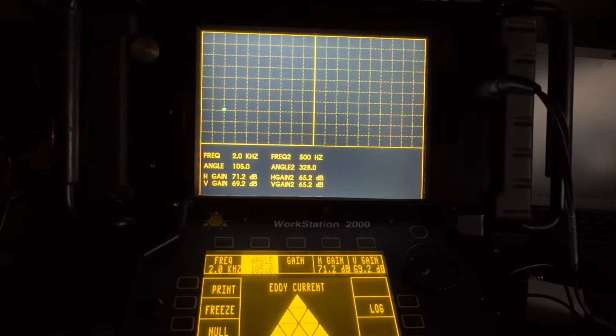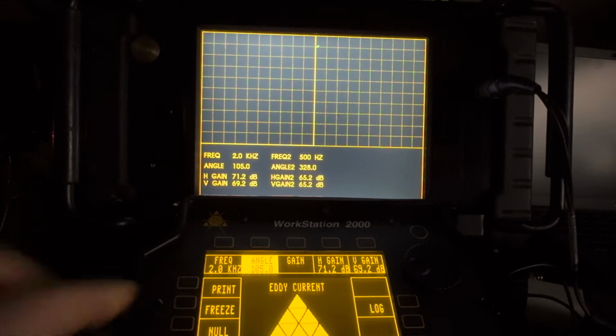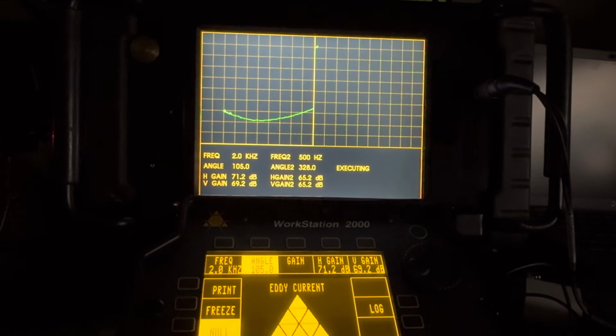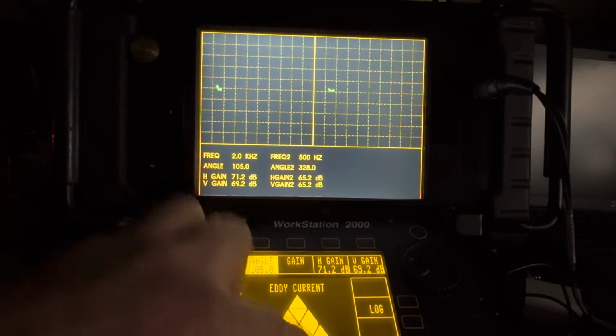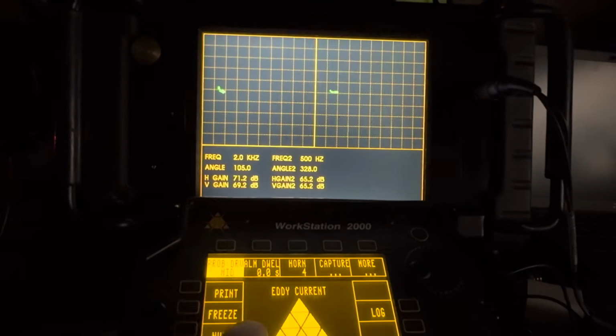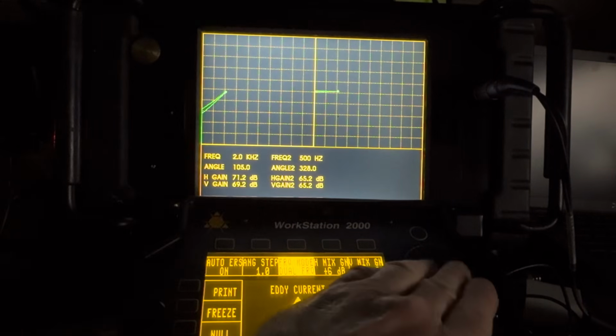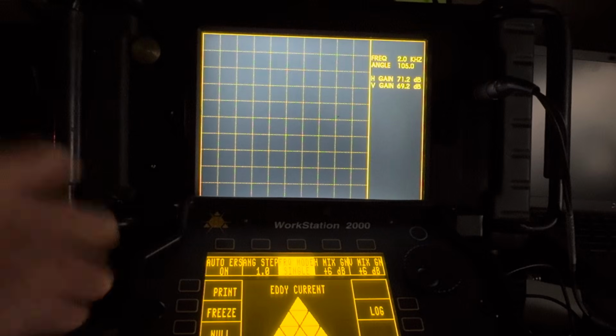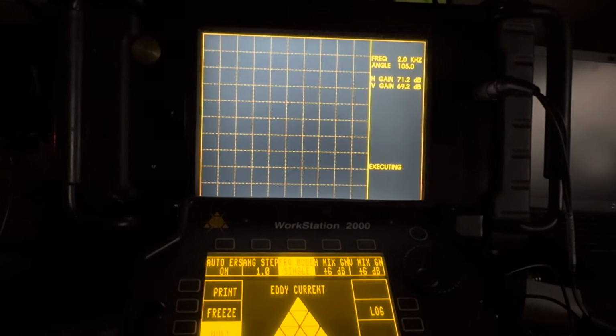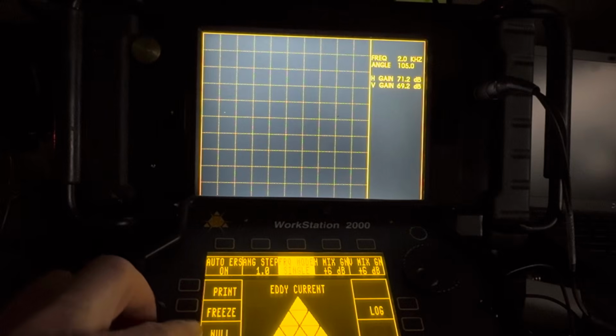And it's kind of the same thing, right? Your procedure is going to have you calibrate in such a way that, okay, and I'm going to have to balance. Let's hit the balance button. I don't really need 2 frequencies here, so let me go into the setup, and let me go to single frequency mode. Okay, here we got 2 kilohertz. I could have used a slightly different frequency. This probe goes all the way down to 300 hertz. It's a smaller probe. All right, let's hit the old null button.